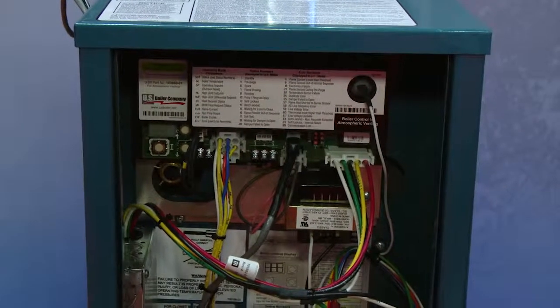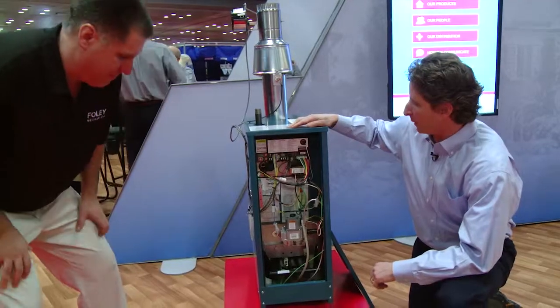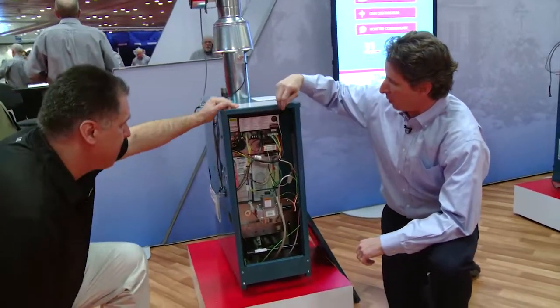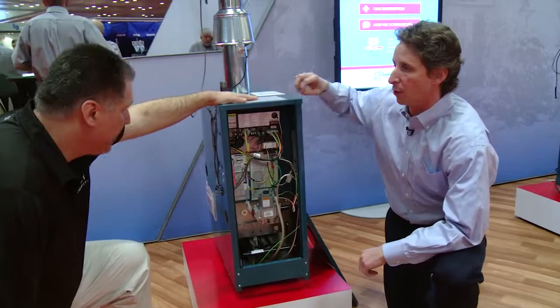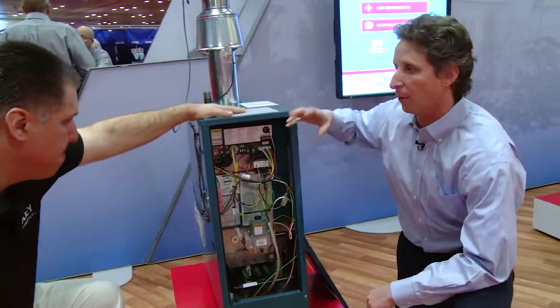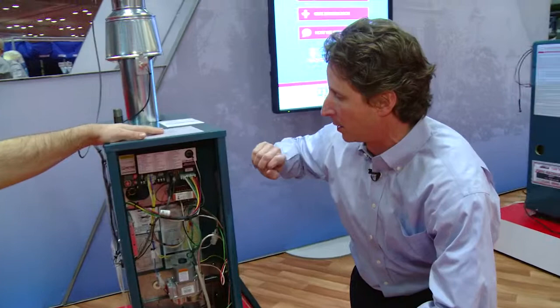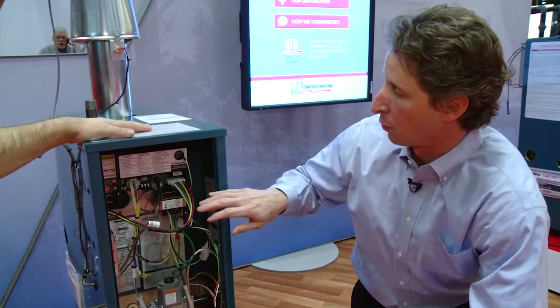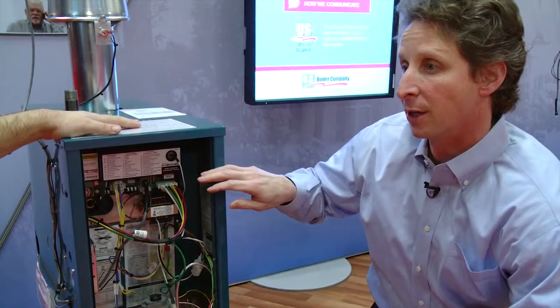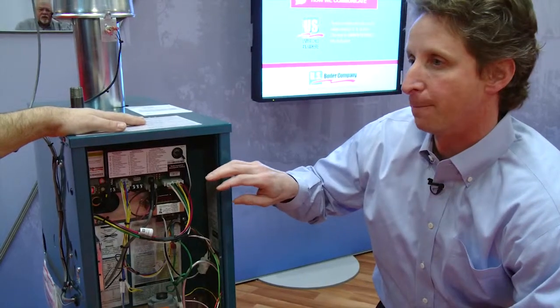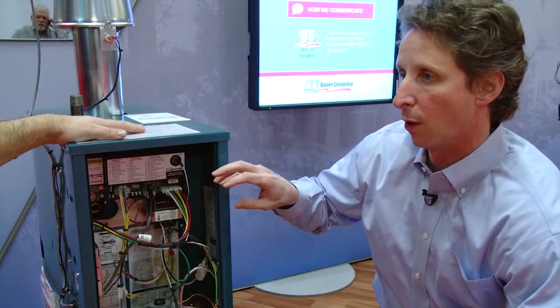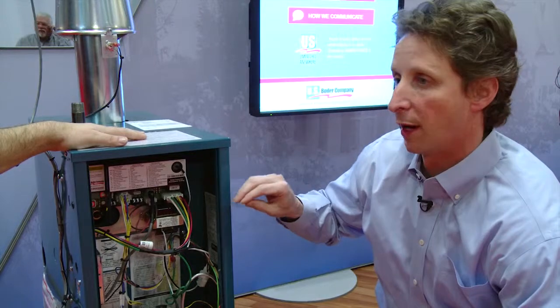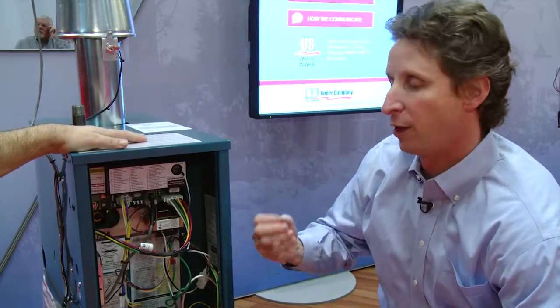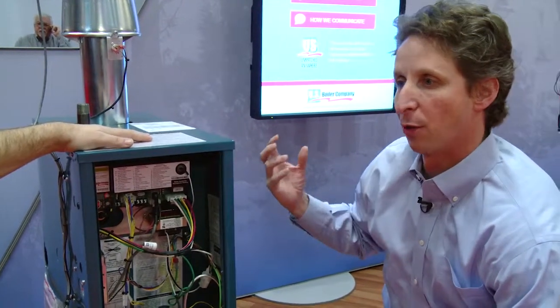When we changed the controls options late last year, we went to this Honeywell integrated control. We now use electronic sensors versus the old mechanical L4006s or 4080s you might have seen. One of the nice things about this control is we've added an extra set of relays, so you can pull off both your domestic priority for your hot water indirect heater, as well as one extra zone. As a contractor, you don't need to go out and get that extra relay or potentially buy a small zone panel. You can pull 2 zones right off this without any real troubles.